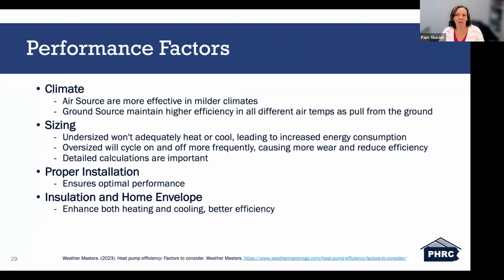So there are some performance factors of heat pump systems you also need to take into consideration. There's a number of key items here, such as climate, sizing, proper installation, and insulation and home envelope. When you're dealing with climate and weather conditions, efficiency is greatly impacted by the climate. Air source systems are typically more effective in milder climates, as extreme temperatures can reduce their efficiency. Ground source, or geothermal, may maintain higher efficiency regardless of air temperature because they are exchanging heat from the ground to the home, which remains at a more constant temperature.